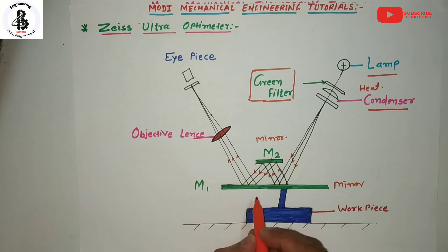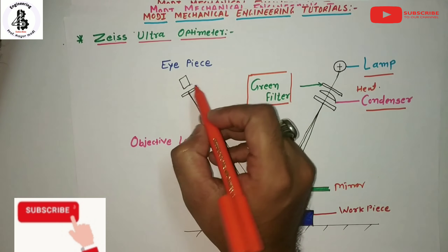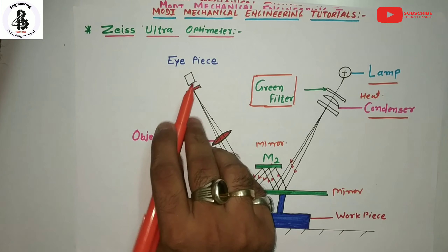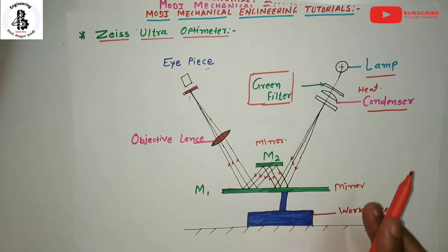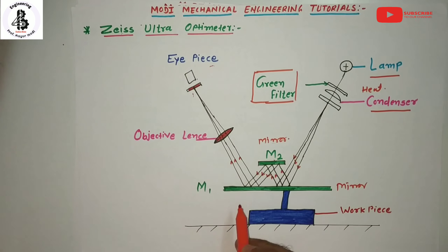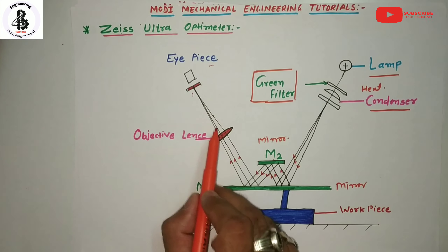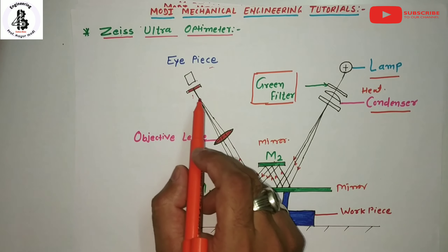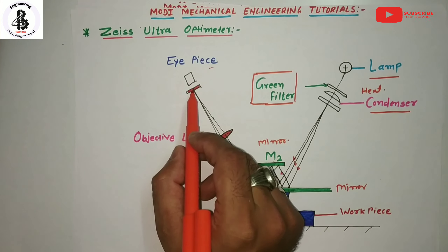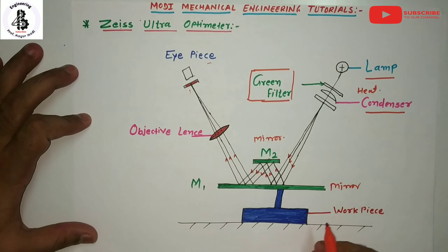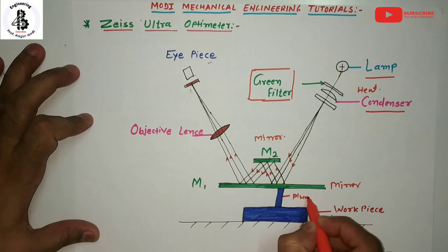The objective lens brings the reflected beams from the first mirror to focus at the transparent graticule, which contains a precise scale. This is viewed from the eyepiece. The reflected rays from M1 pass towards the objective lens, focusing at the graticule, and you can easily take readings from this eyepiece lens.